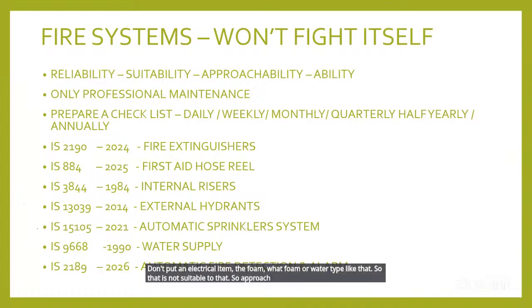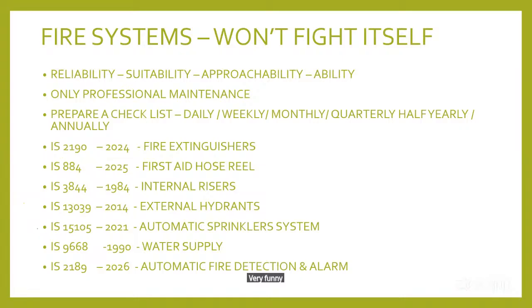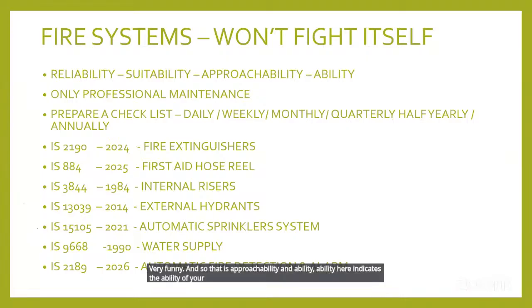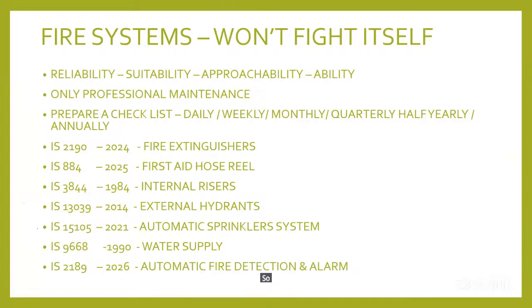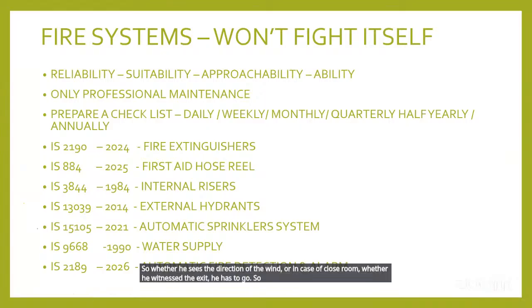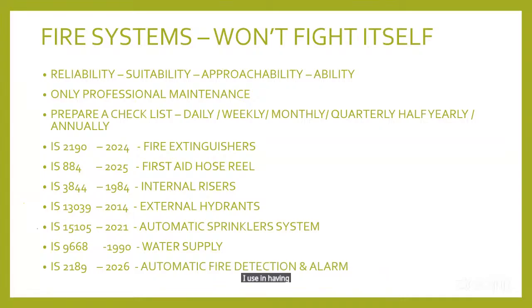Then approachability. Extinguishers are there and hydrants are there, but they are blocked by a storage system or by a parked car, which is very funny. That is approachability. And ability here indicates the ability of your trained people. In case of emergency, how fast and how smart can he take and use the extinguisher, what distance does he keep between the base of the fire and the nozzle of the extinguisher, does he see the direction of the wind, and in a closed room, does he note the exit he has to go to. How smart and skilled he is, that is important. That is the ability. These four criteria must be there, otherwise there is no use in having the firefighting system in your premises.